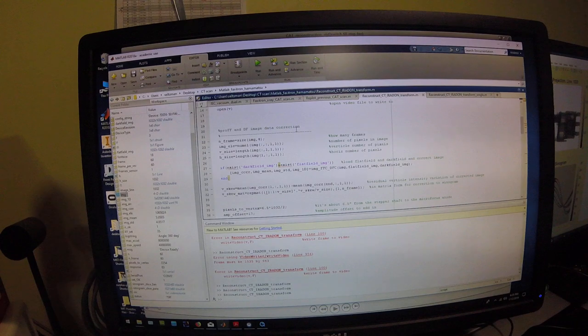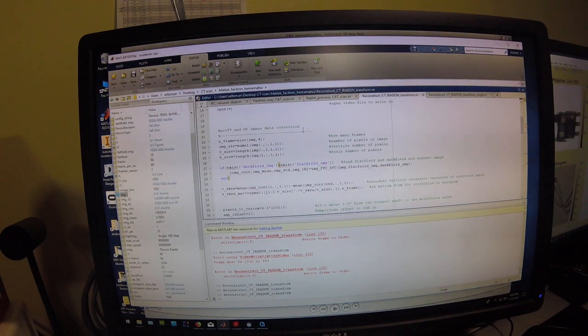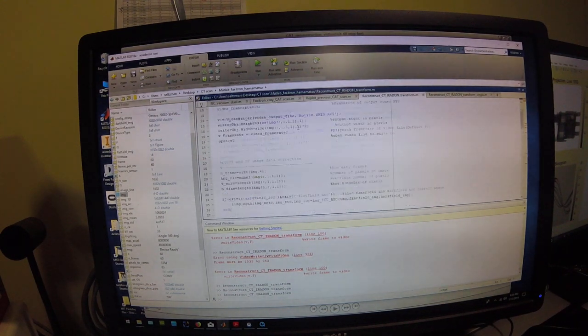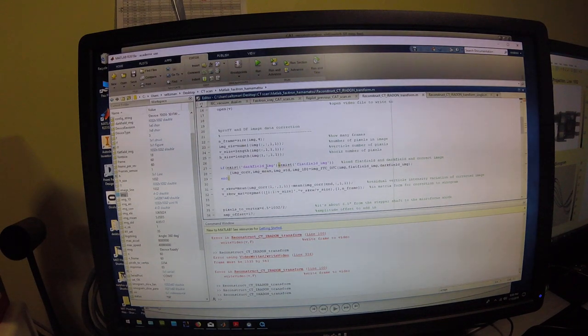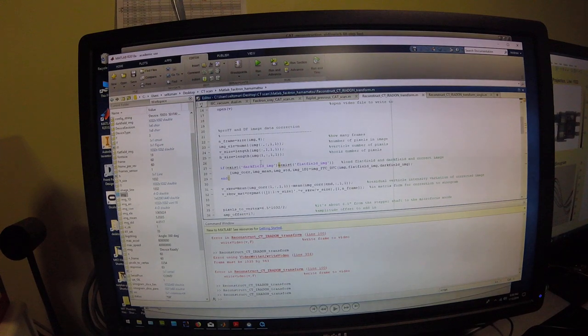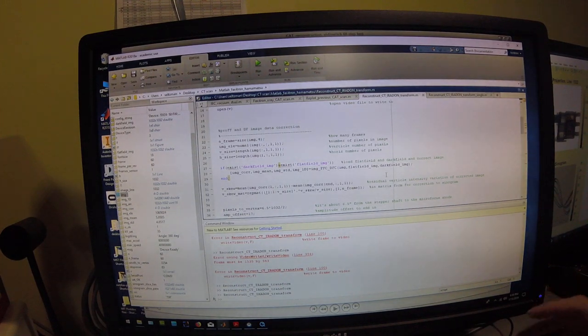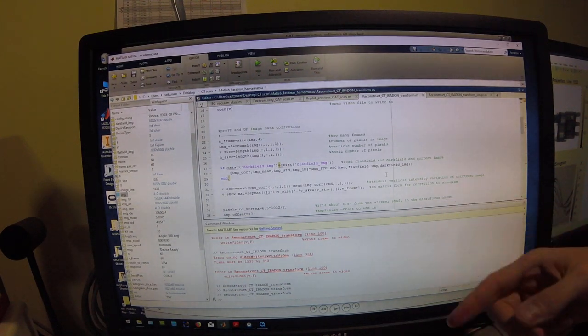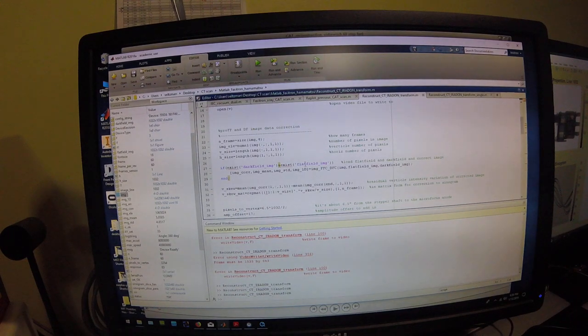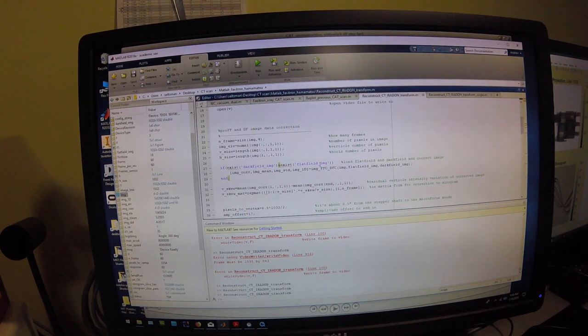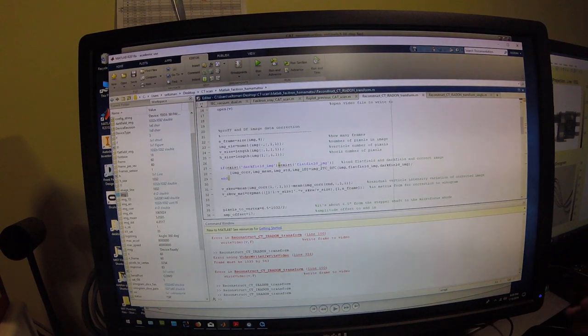It does this over a number of slices for the rotating image. So first what it does is it takes the flat field and dark field images that were previously generated and it applies these to all the images in that picture of the switch rotating. That corrects for the dark field noise and inhomogeneity in the sensor response and in the x-ray beam.